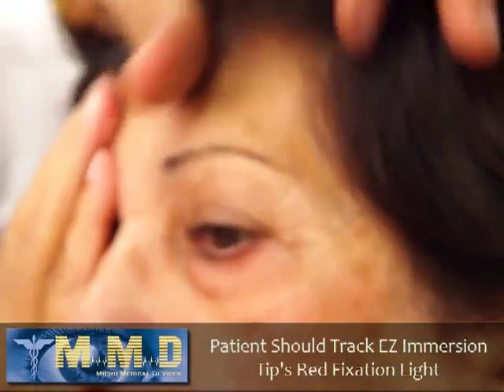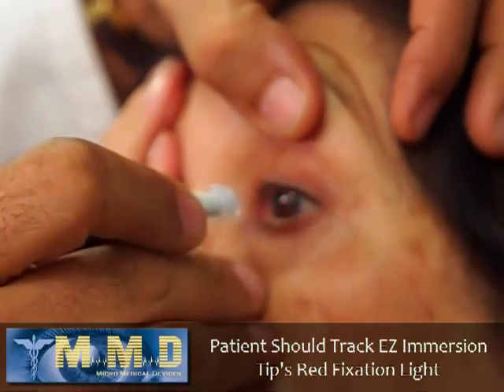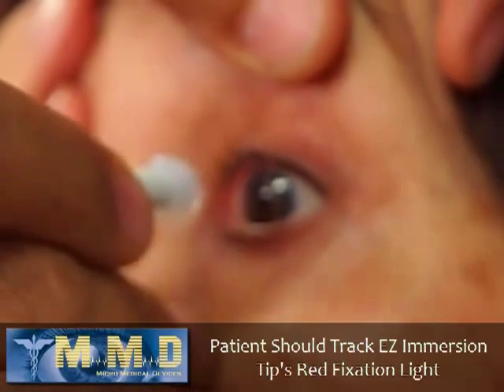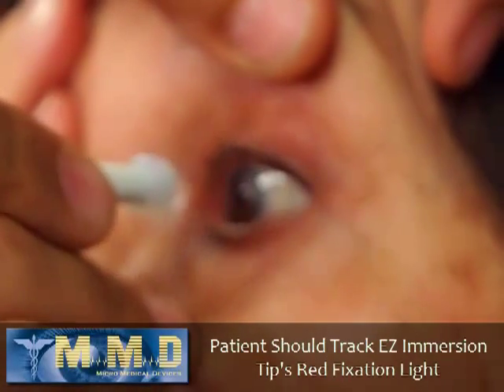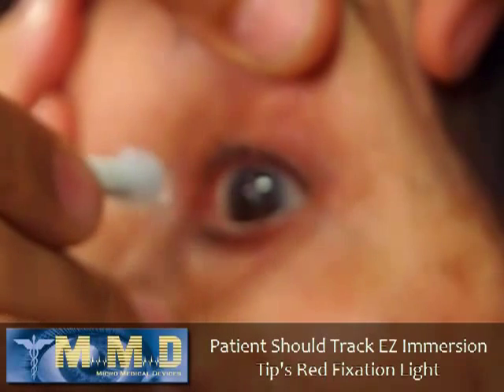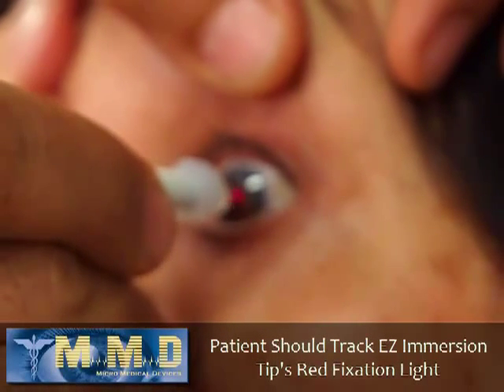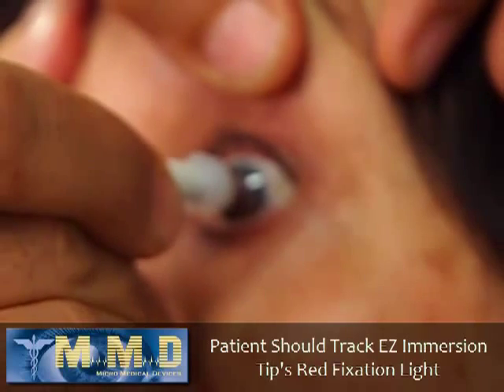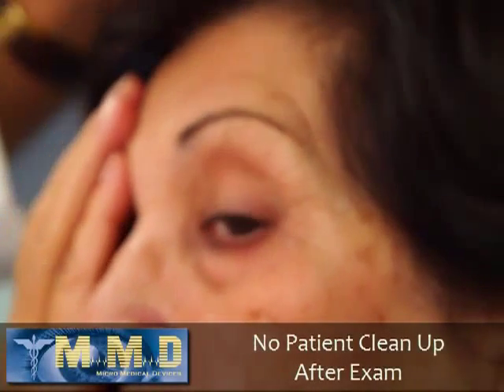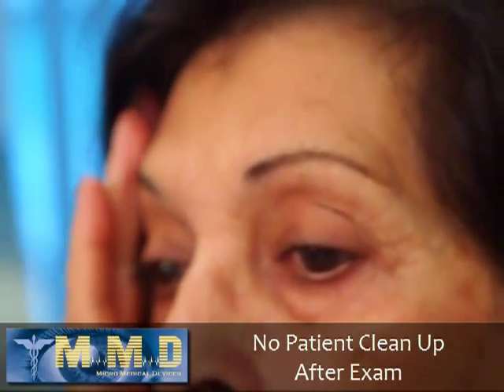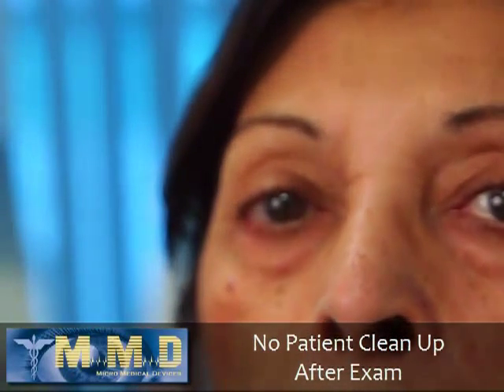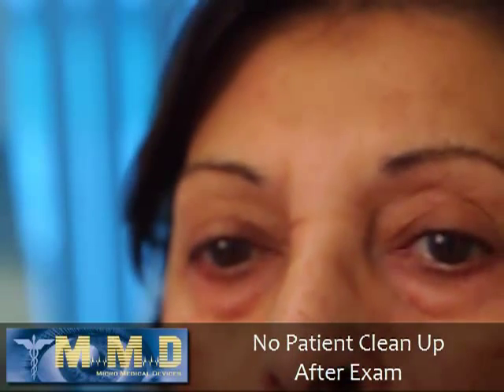So the main thing to remember is if the machine is not capturing when you touch the eye, don't press on the eye. Just hold it stable and ask the patient to look at the blinking light. Please look at the blinking light. So first I move it a little bit to make sure that the patient is fixating properly, and then just bring it close enough, and then you're done. Basically that's all it takes to do a successful immersion biometry without any mess on the patient.